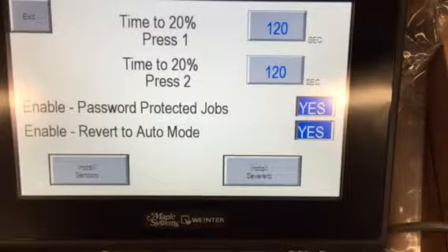It will prompt you to arm your web break detection system at that time. If you don't respond within 15 seconds, it will shut the system down. The reason we do this is it's a redundancy feature and allows you to run perfectly safe. However, if you're missing one of your signals, you do need to have an electrician come in and repair that. But you can override the system and arm your web break detection system by pressing that button when it does come up.